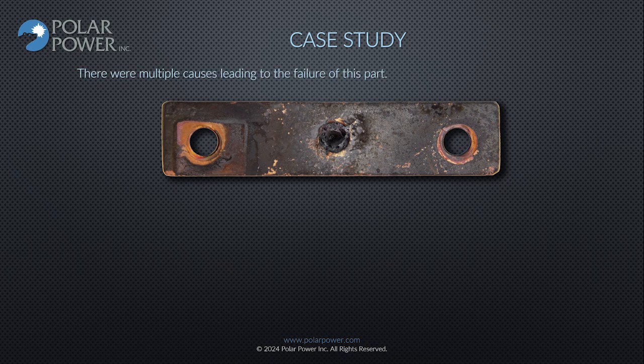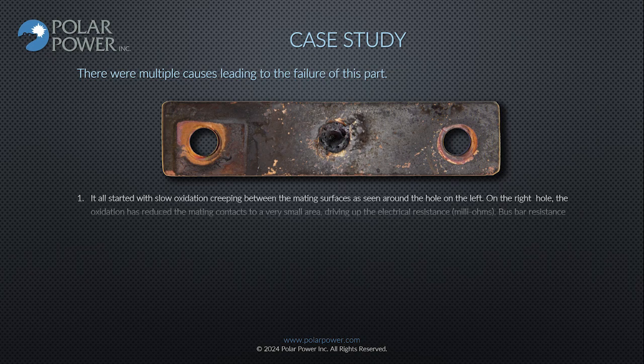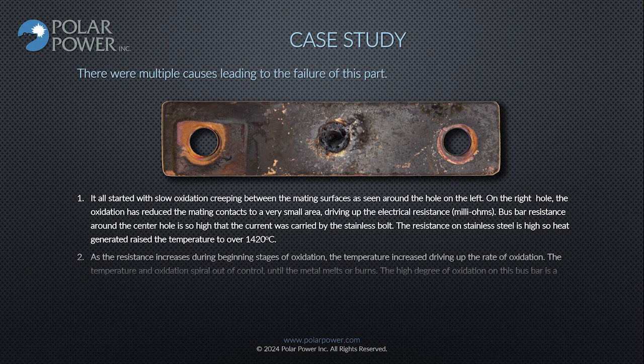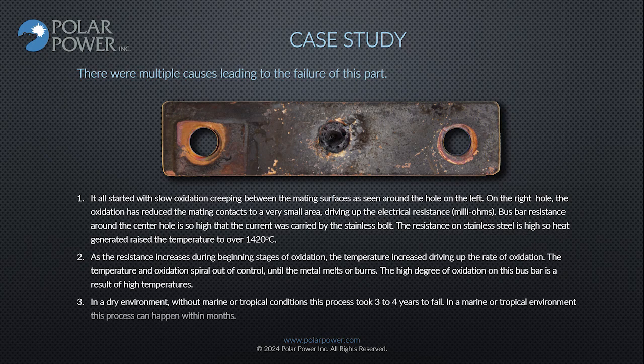It all started with slow oxidation, creeping between the mating surfaces, as seen around the hole on the left. On the right hole, the oxidation has reduced the mating contacts to a very small area, driving up the electrical resistance to milliohms. Bus bar resistance around the center hole is so high that the current was carried by the stainless bolt. The resistance of stainless steel is high, so the heat generated raised the temperature to over 1420 degrees Celsius. As the resistance increases during the beginning stages of oxidation, the temperature increased, driving up the rate of oxidation. The temperature and oxidation spiral out of control until the metal melts or burns.